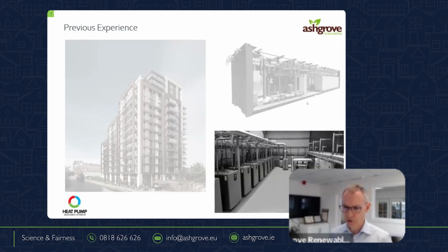So you can see a heat exchanger. You won't make it out in that thing, but there is a heat exchanger. You have a series of pumps. We're taking the energy from a lake, and we're using it then to drive heat around a factory, and hot water, and drying facilities. But that's all running from on-site wind turbines, and as the wind slows down, we're able to individually slow down each of the compressors by controlling the frequency to the motors.